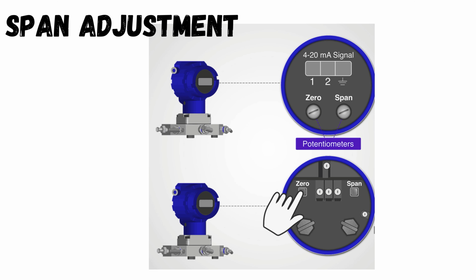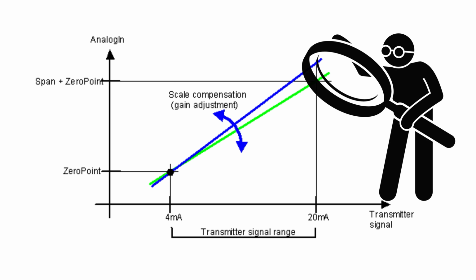Span adjustment. This involves calibrating the transmitter to ensure that it accurately measures across its full range. Span adjustment sets the full-scale output of the transmitter so that it matches the expected range of the process variable.